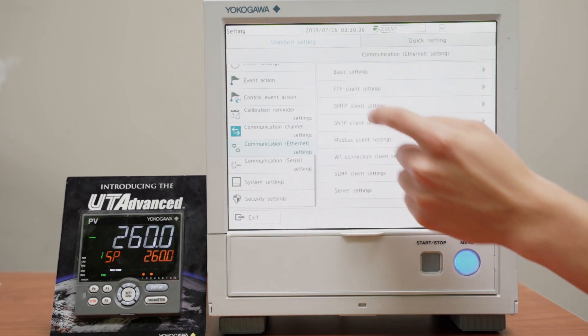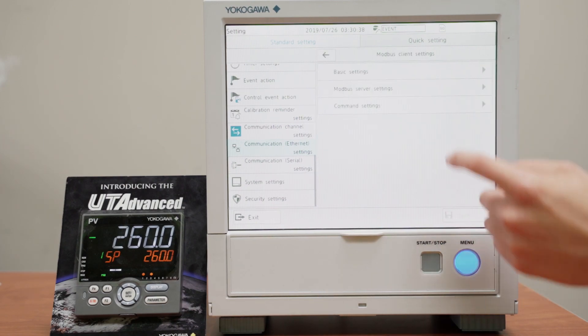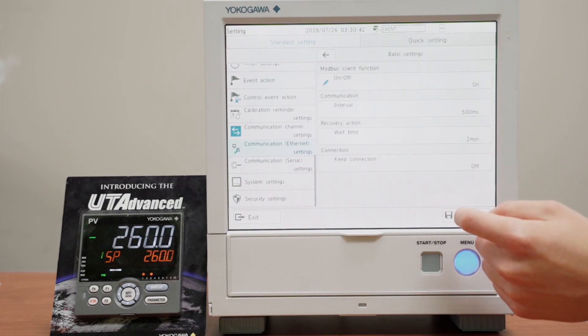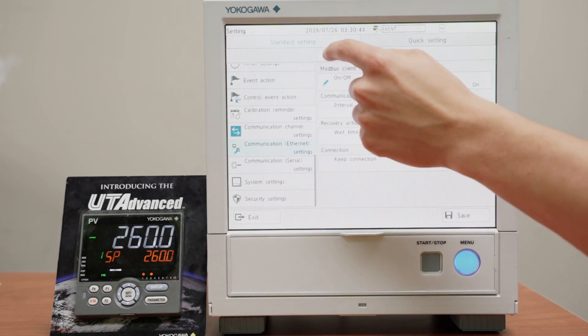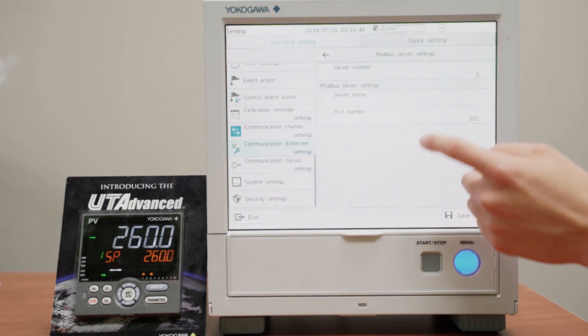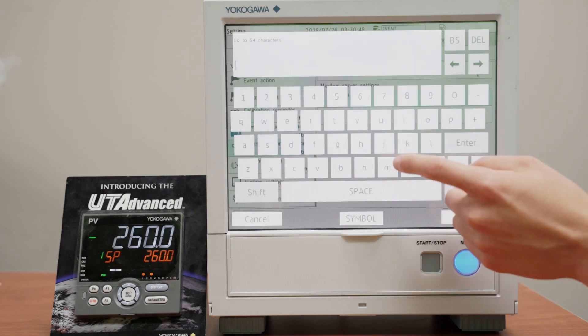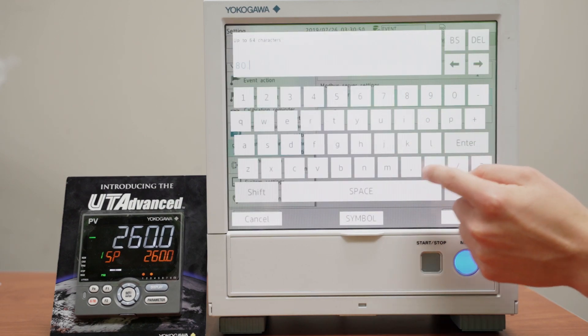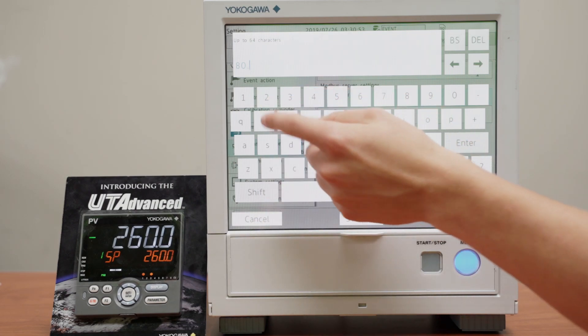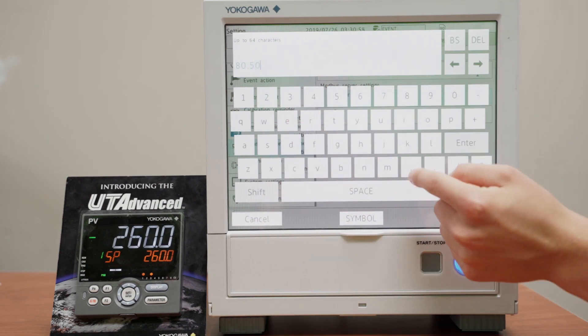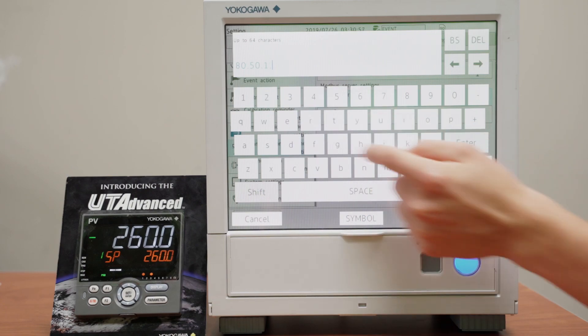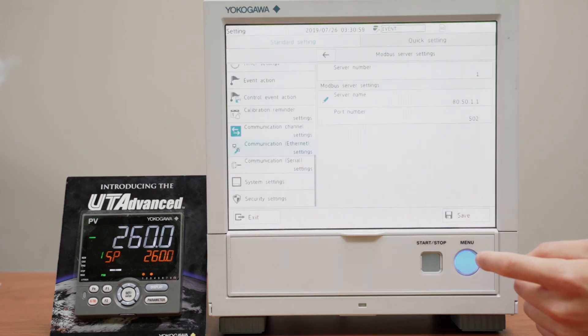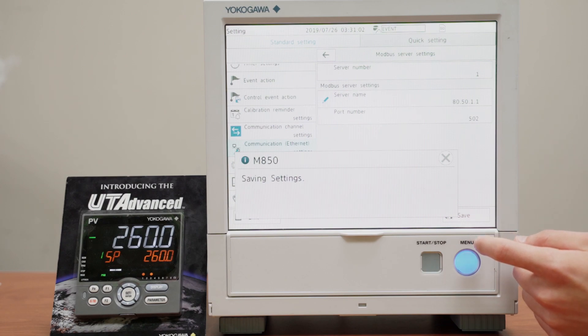Next, we're going to go back, go into Modbus client settings, basic settings, and we'll turn this on. We can leave all these settings the same, go into Modbus server settings, and the server name is going to be the IP address of our UT55. Port number can stay the same, we'll save this.